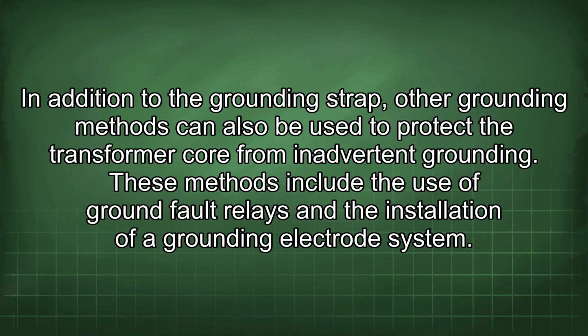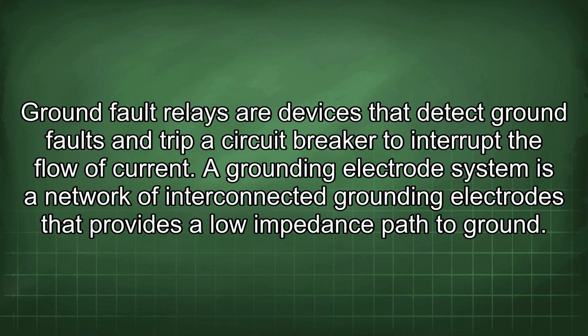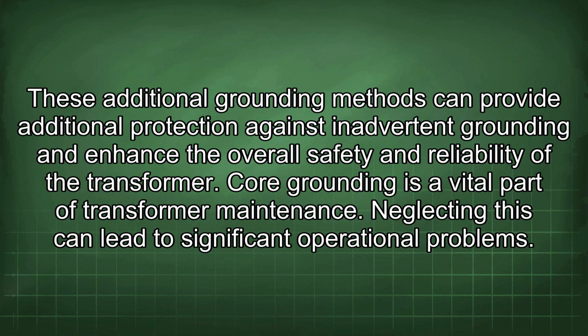In addition to the grounding strap, other grounding methods can also be used to protect the transformer core from inadvertent grounding. These methods include the use of ground fault relays and the installation of a grounding electrode system. Ground fault relays are devices that detect ground faults and trip a circuit breaker to interrupt the flow of current. A grounding electrode system is a network of interconnected grounding electrodes that provides a low impedance path to ground. These additional grounding methods can provide additional protection against inadvertent grounding and enhance the overall safety and reliability of the transformer.